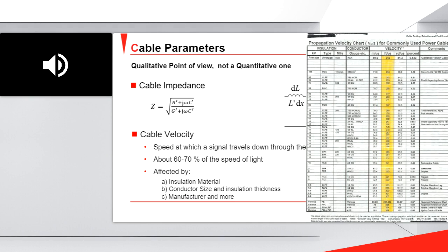Normally, all the thumpers and all the cable fault locators handle an average of the propagation velocity for all the different cables, and we also have lists in the thumpers. We have a list, and we can select the correct propagation velocity for the cable in which I'm working. So this is not a big problem, but this is also a very important parameter.